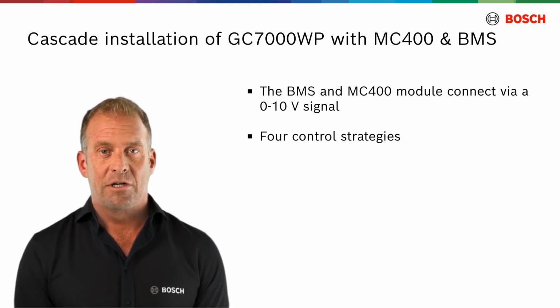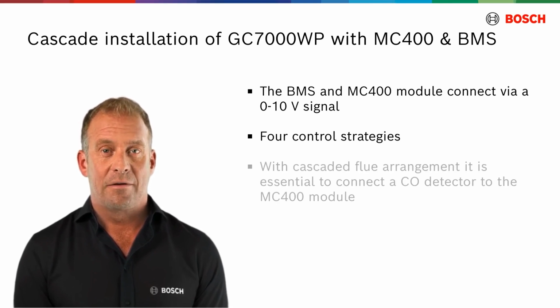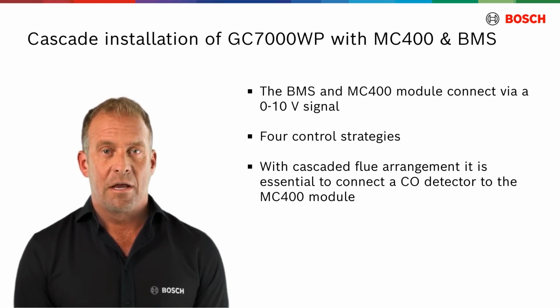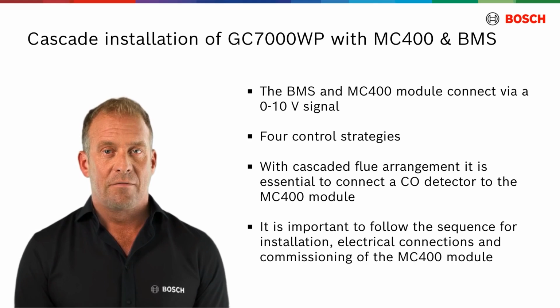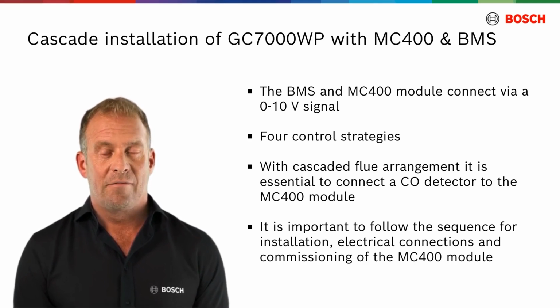For the safe operation of the boiler cascade with cascaded flue arrangement, it is essential to connect a CO detector to the MC400 module. Additionally, it is important to follow the sequence for installation, electrical connections, and commissioning of the MC400 module. In the next video, we examine a heating and hot water system using a cascade of GC 7000 WP and a controller which enables internet connection, remote monitoring, and diagnostics complying with Part L building regulations.